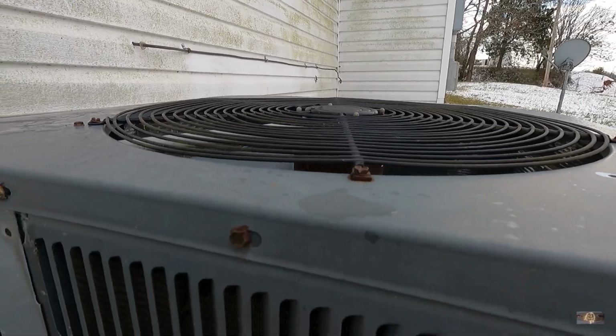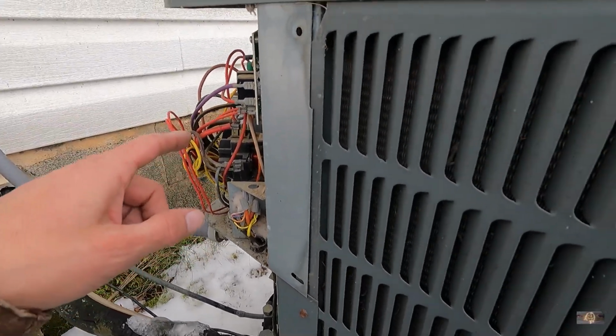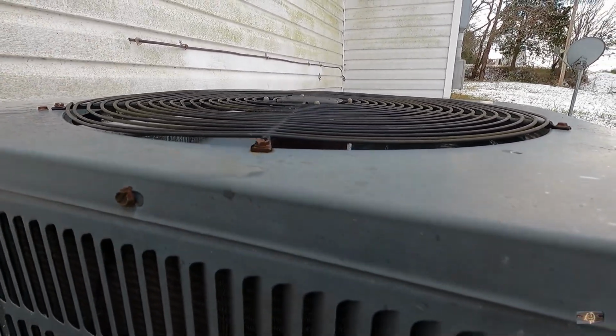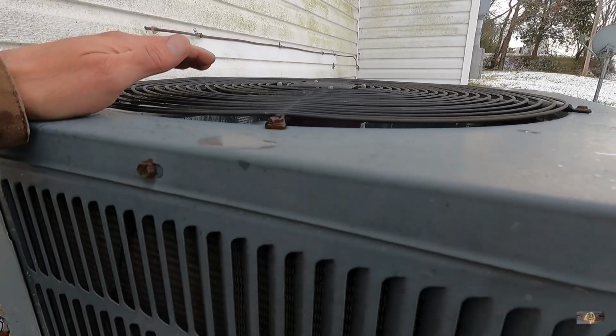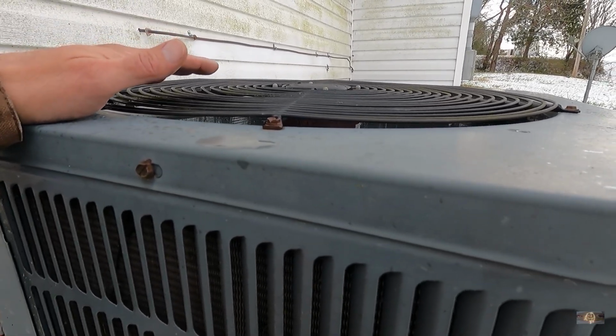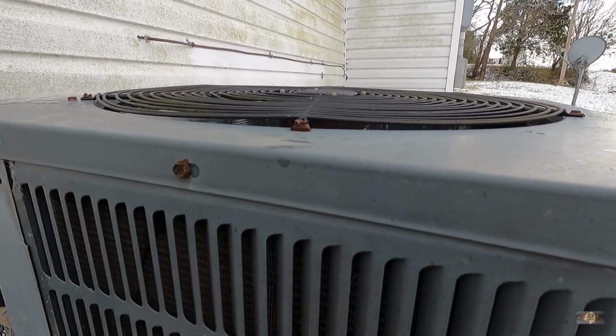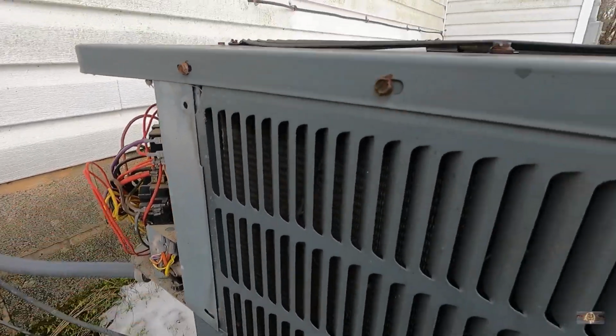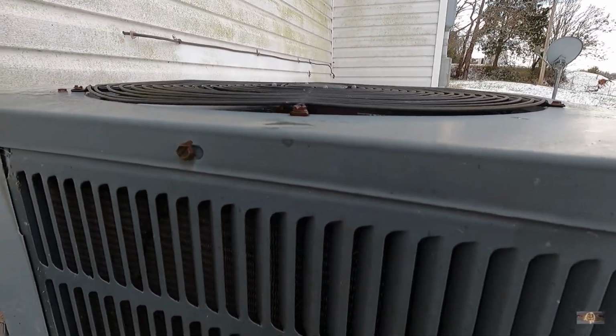So I'm thinking that motor is an issue. I did amp draws on the motor. I'm pulling 1 to 1.1 amps. The full load amps on this motor is 0.9, so we are over amping. And on the compressor, I was pulling 8.1 amps.